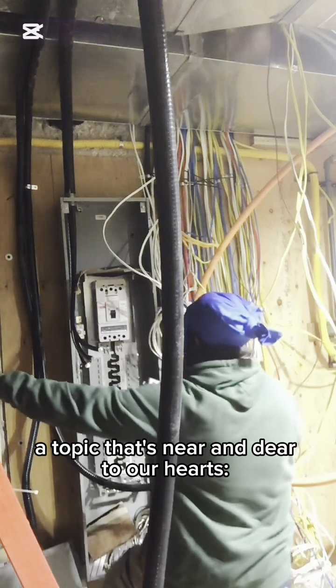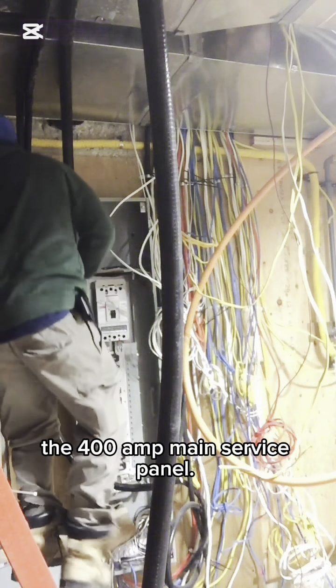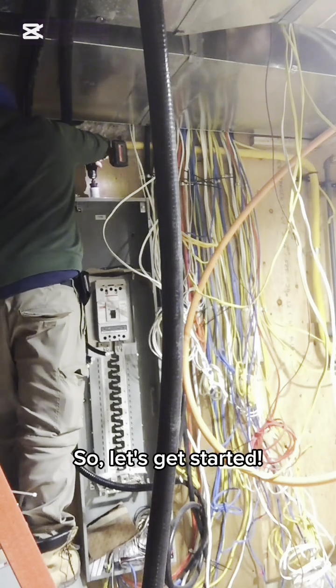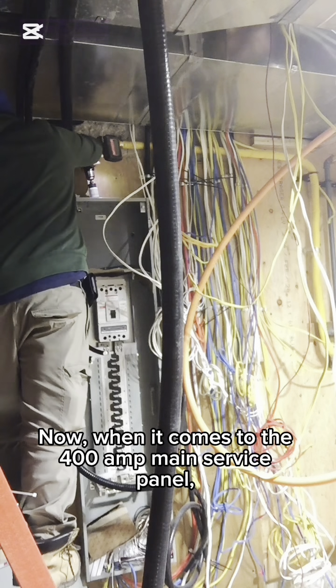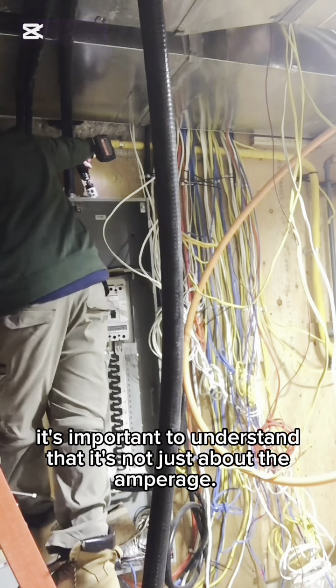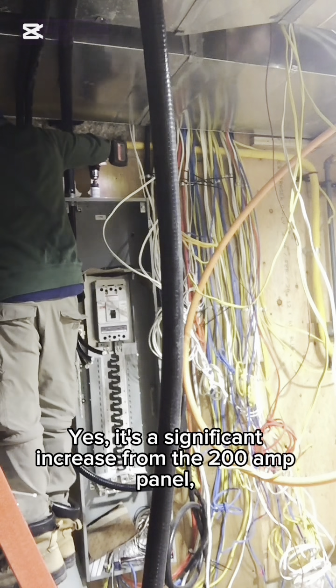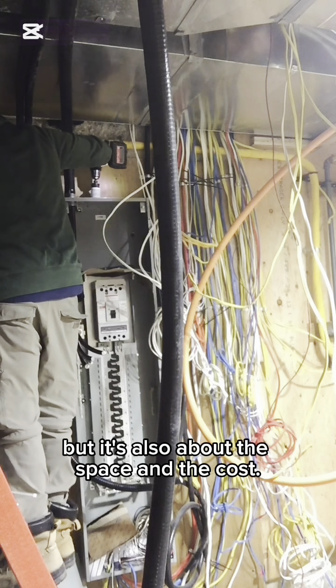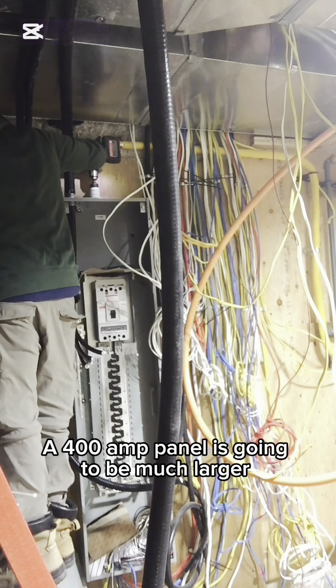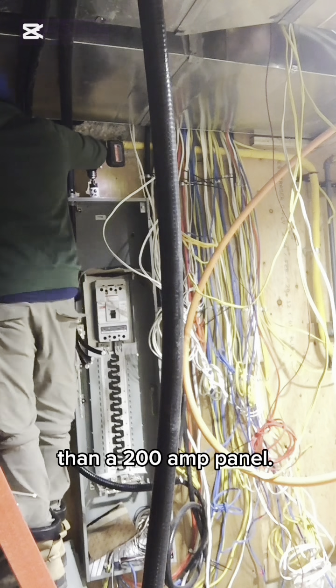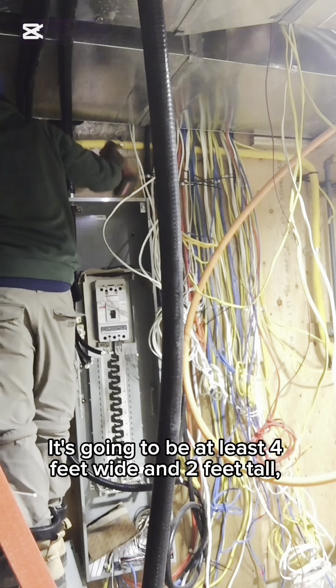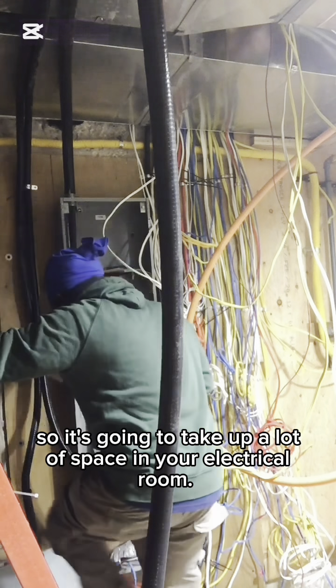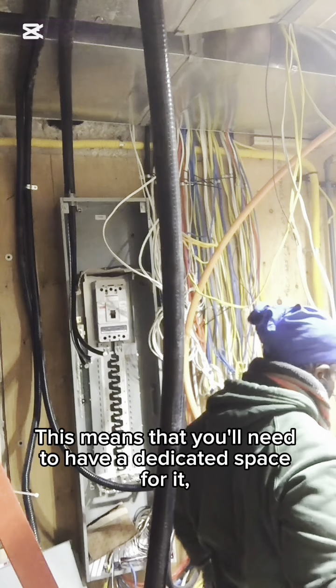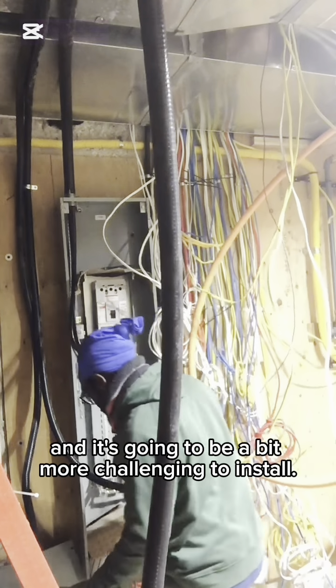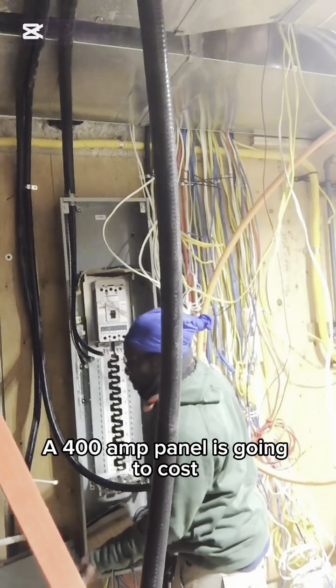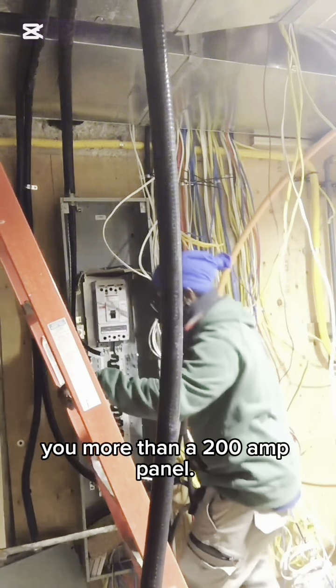What we have here is a 400 amp electrical panel, and the installation involves the main feeders coming in, which are 400 amp for the 400 amp service. These are 250 KCMIL parallel feed cables that I'm running, and the cables are the same length. With parallel runs, you have to make sure the lengths are all the same. I'm landing them on the top of the 400 amp distribution service, and as you can see, I have one set of cables landed.